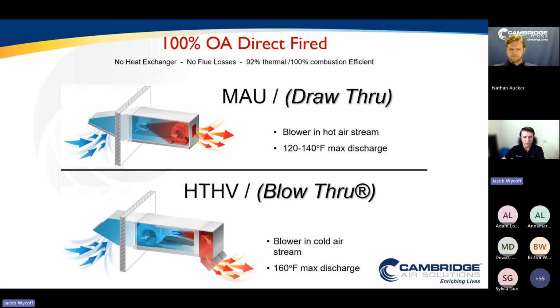That's just because the blower components really can't handle going above that by much. So your belts, your bearings, your motors are only rated for specific temperatures, and trying to run those even at 140 degrees and especially greater than that is really going to reduce the amount of life that you're going to get from those components. And you're going to be frequently replacing components much more often than would be reasonable.